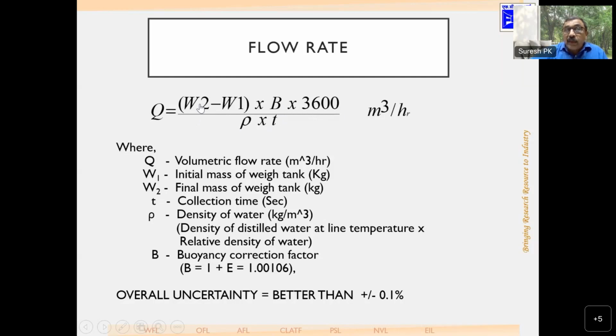The uncertainty in the standard mass, the calibration of the standard mass, affects the final uncertainty. The buoyancy correction factor is a factor which is used when you are calibrating the weighing machine using mass. The mass displaces some amount of air, which applies a certain amount of buoyancy force on the weighing machine and its indication.